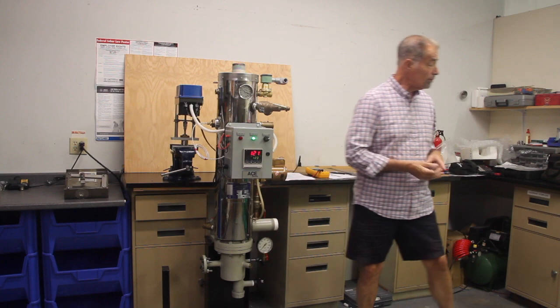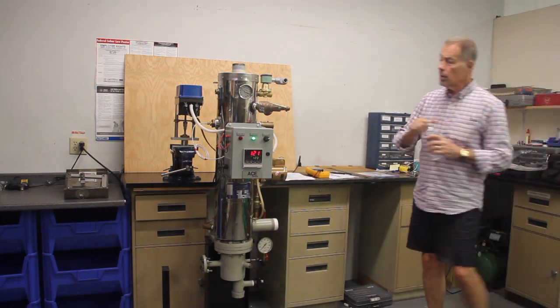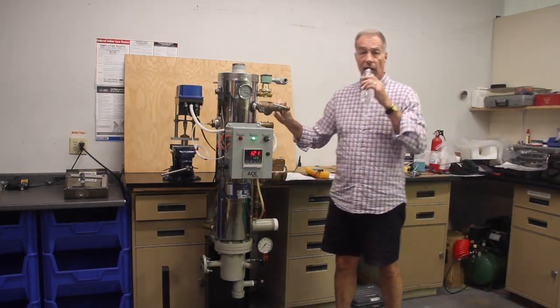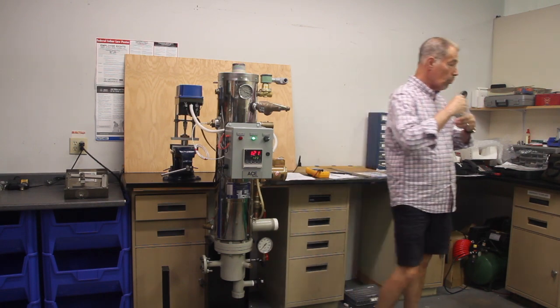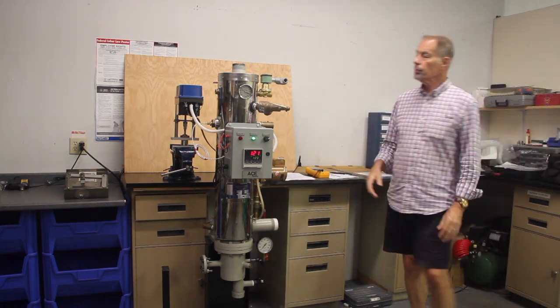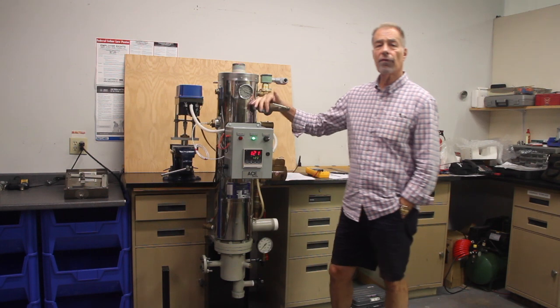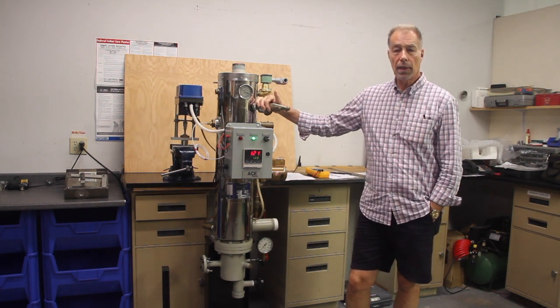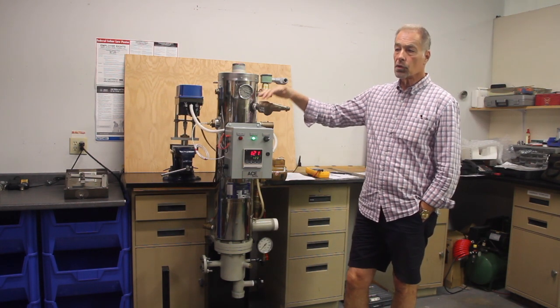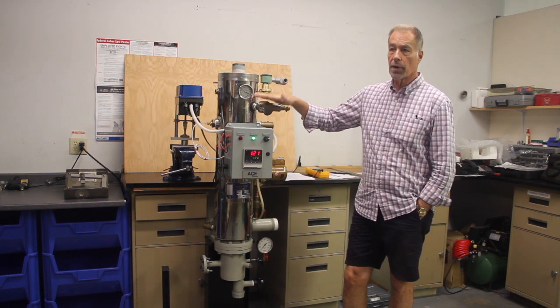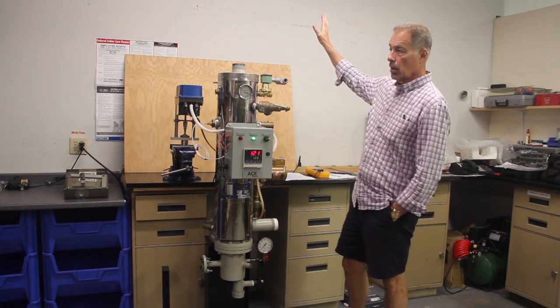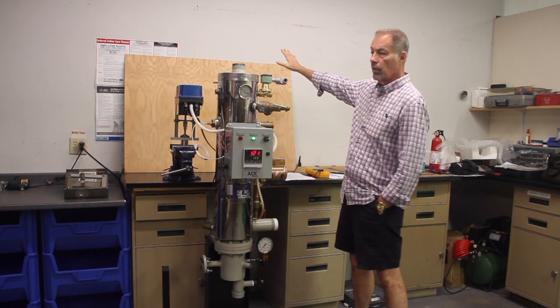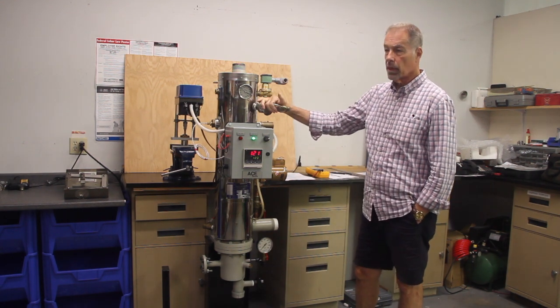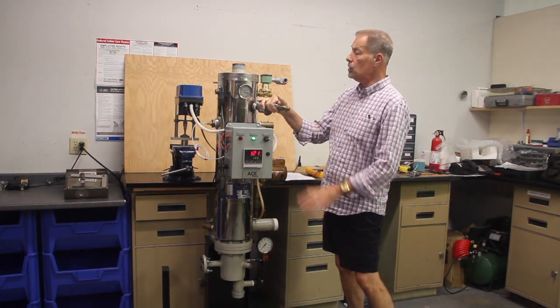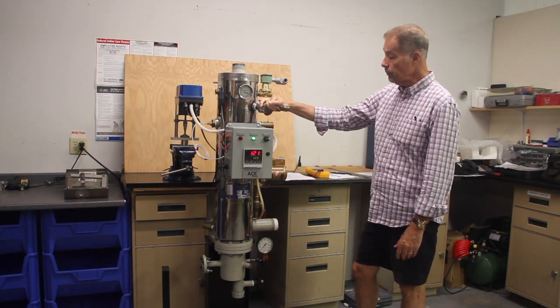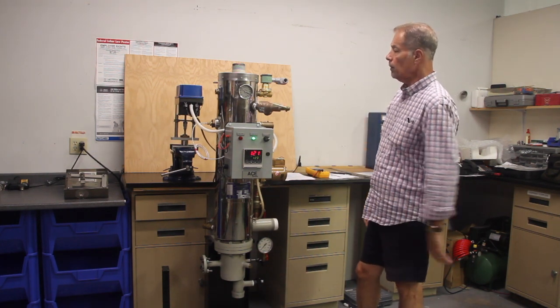ASME relief valve on the heater. This is only a pressure relief valve. Excuse me. It is not a temperature and pressure relief valve. It doesn't need to be by the ASME code, because there's no direct fuel being fired here on this. The TP relief valve is on the boiler. This only has to be a relief valve, which is set for 150 pounds or higher. We can go higher. For Colby, it's all 150 pounds.